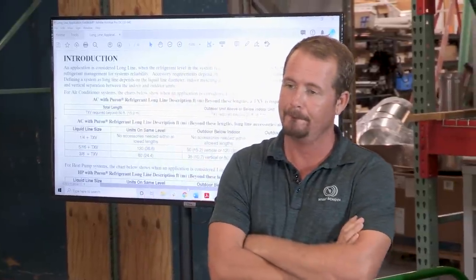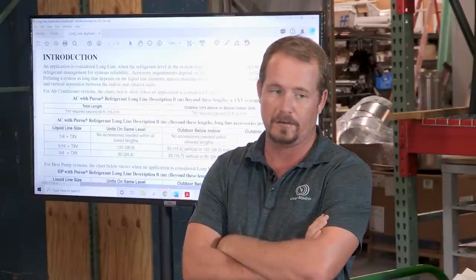Another side note, what's the reason why we don't like burying suction lines for a long distance? Why wouldn't you want to bury a suction line for a long distance? Is this like a side note? No, it's directly related to what we're talking about right now. What temperature is the ground in comparison with the air for most of the cooling season? Colder, right? And when the system goes off, what is the lowest point in the system now if you have a buried suction line?